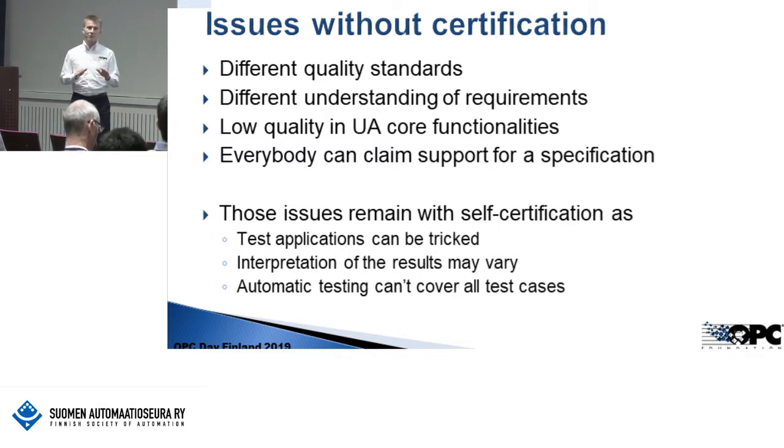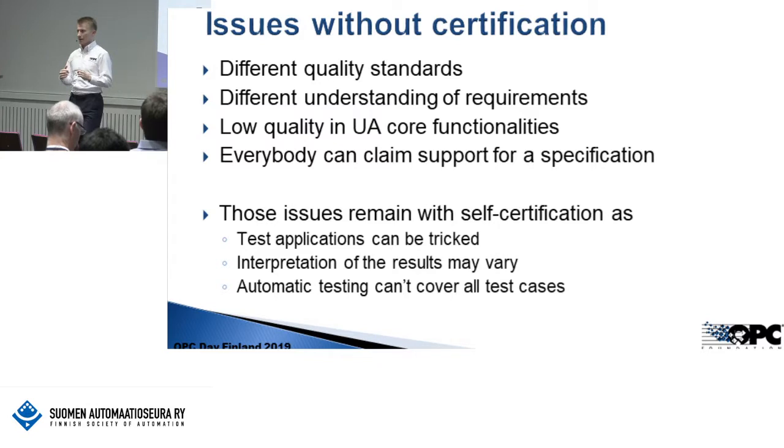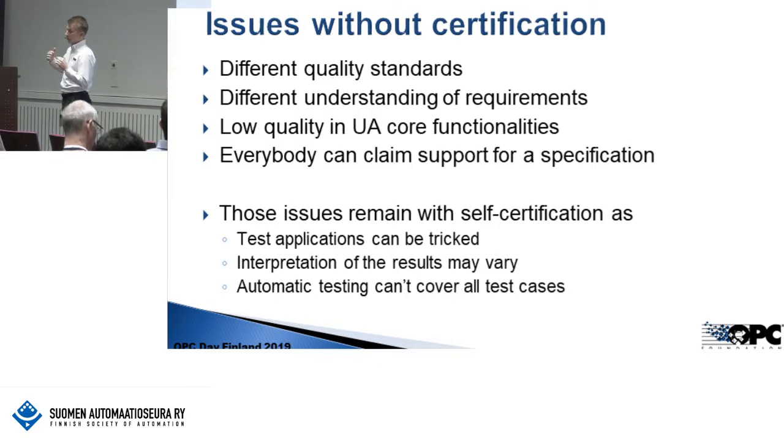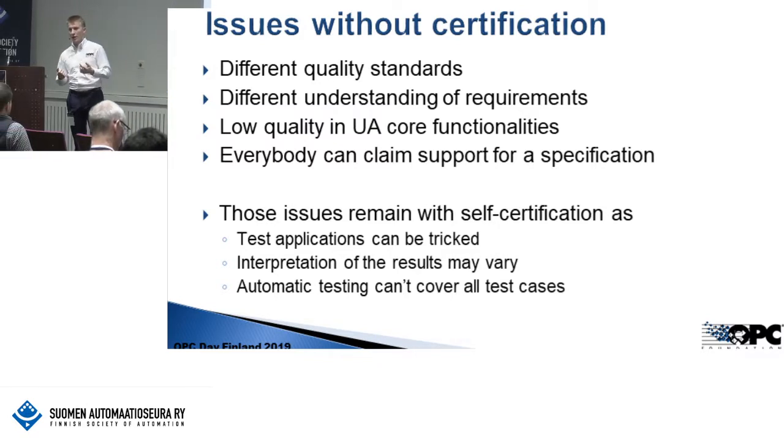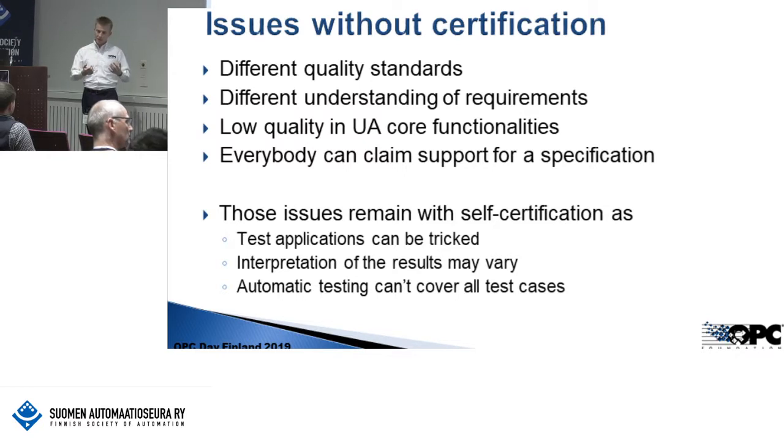And that is the baseline for certification, because that is exactly how we do that. So when a product comes to certification, it defines all the profiles and facets that it supports. And by having them, we do get all the conformance units, and with that, the list of test cases that need to be executed. So this is the baseline for certification, as well as your in-house testing, because the beauty of that, obviously, is you do have all the test cases defined for your internal testing as well, right?